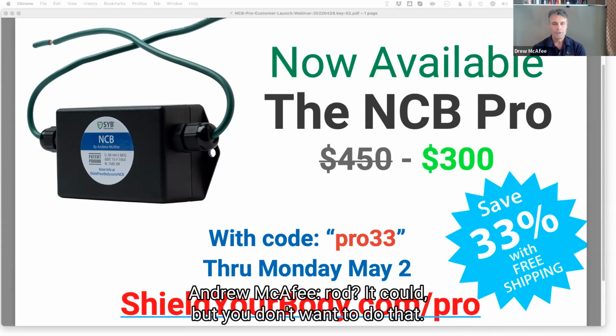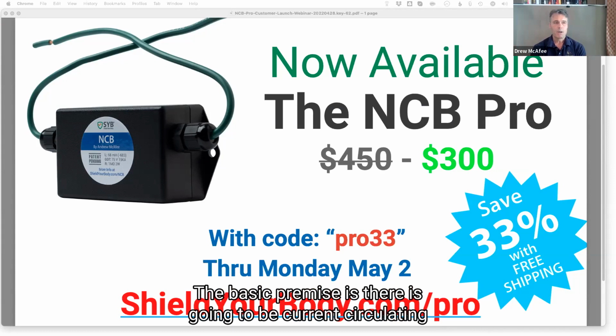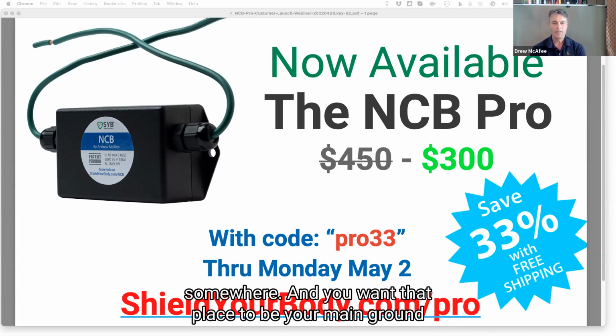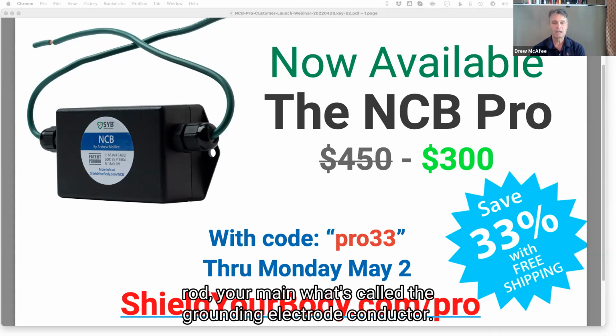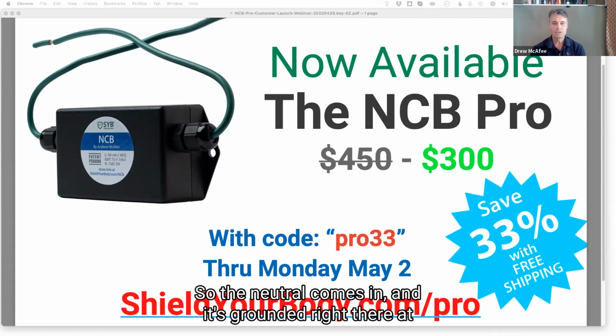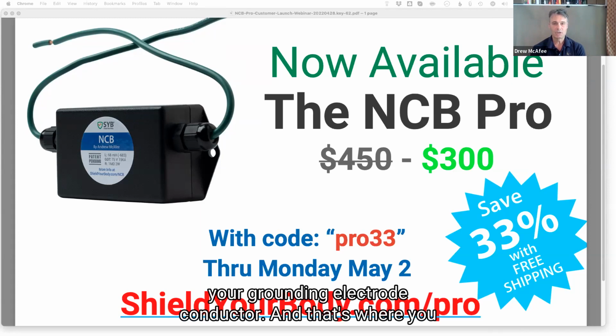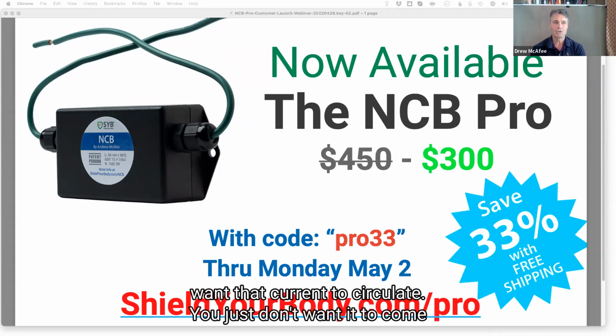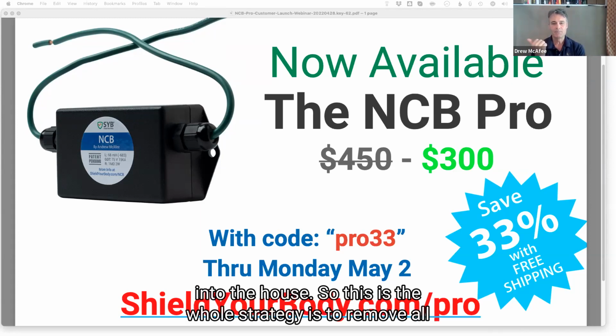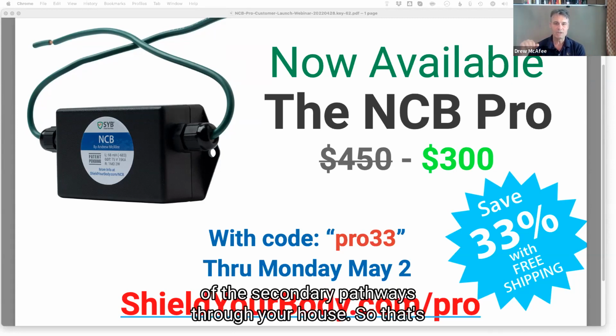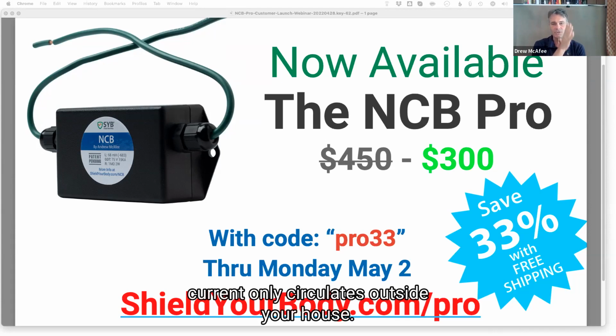It could, but you don't want to do that. The basic premise is there is going to be current circulating somewhere, and you want that place to be your main ground rod, your grounding electrode conductor. The neutral comes in and is grounded right there at the grounding electrode conductor, and that's where you want that current to circulate. You just don't want it to come into the house. So the whole strategy is to remove all the secondary pathways through your house so that current only circulates outside your house.